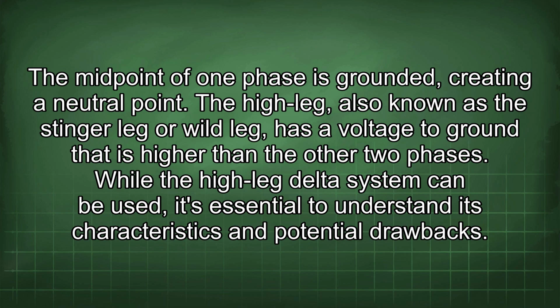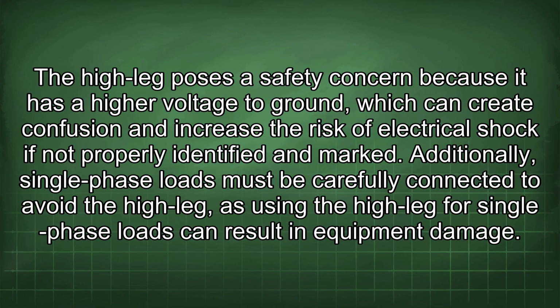While the high leg delta system can be used, it's essential to understand its characteristics and potential drawbacks. The high leg poses a safety concern because it has a higher voltage to ground, which can create confusion and increase the risk of electrical shock if not properly identified and marked. Additionally, single-phase loads must be carefully connected to avoid the high leg, as using the high leg for single-phase loads can result in equipment damage.